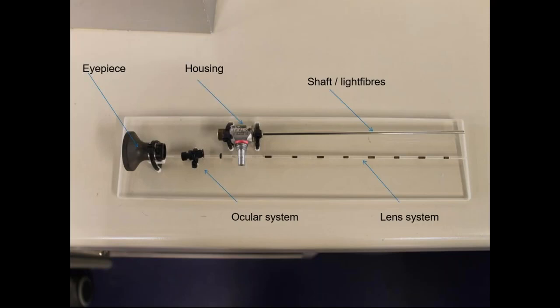And then you can also get the optical image back here by substituting these lenses with a fiber optical bundle, what's known as a coherent fiber bundle, where all the fibers are stacked in order, so it acts like a pixel on a screen. The top right fiber at the distal tip is the same as at the proximal tip, so you can then get an image back. The advantage of using a fiber lens system is it's more flexible, and so often you find that that's used in very thin instruments that need to be more flexible.